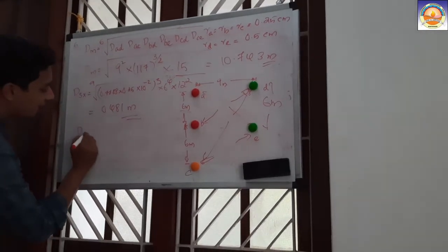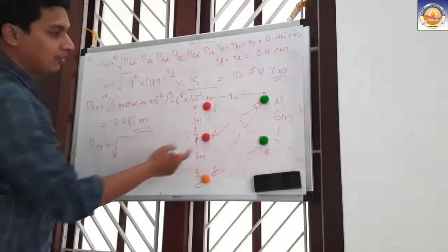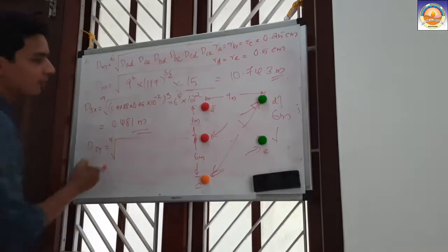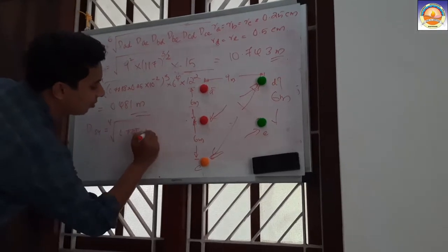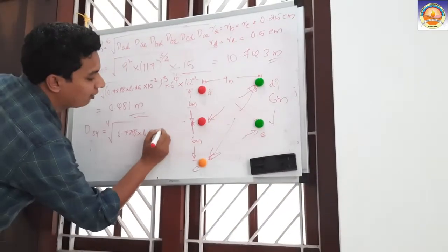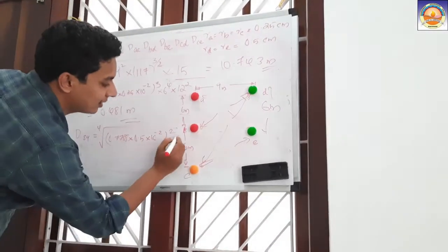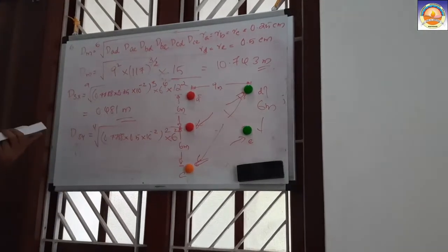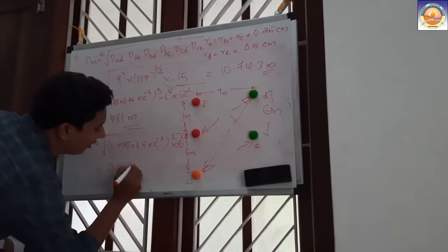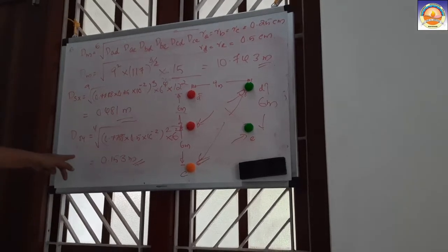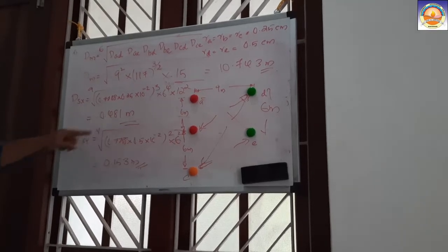For the Y (second) circuit with two conductors, there are N² = 4 terms. The self-GMR uses R' = 0.7788 × 0.5 × 10⁻² m, appearing twice (squared). The distance between D and E is 6 m, giving 6². This yields D_SY = 0.153 m.